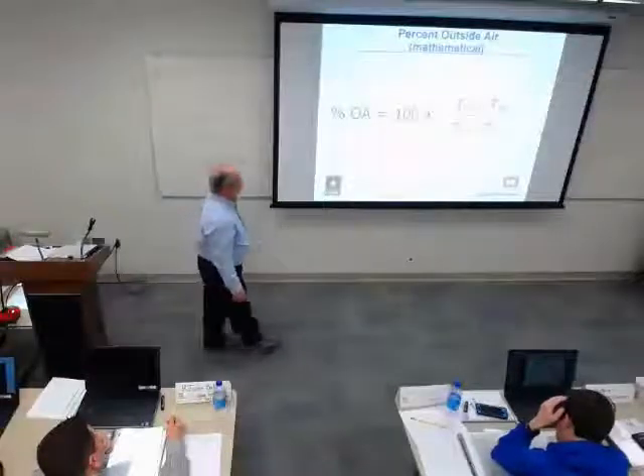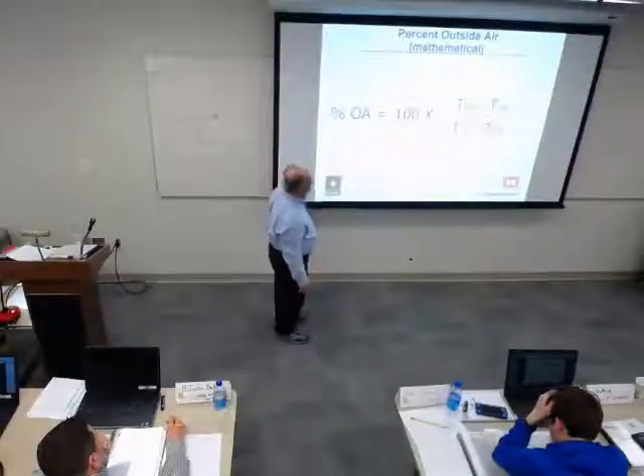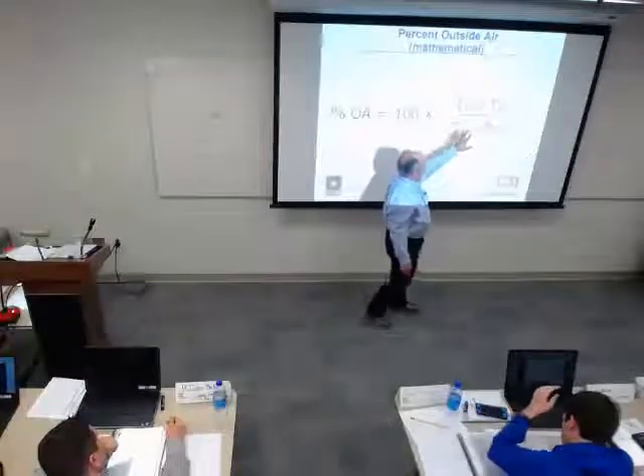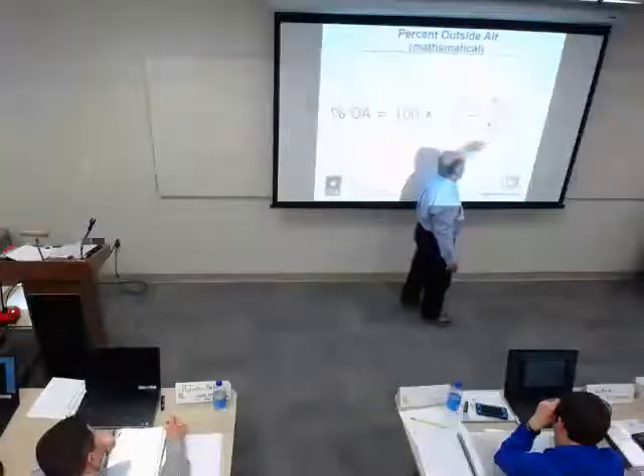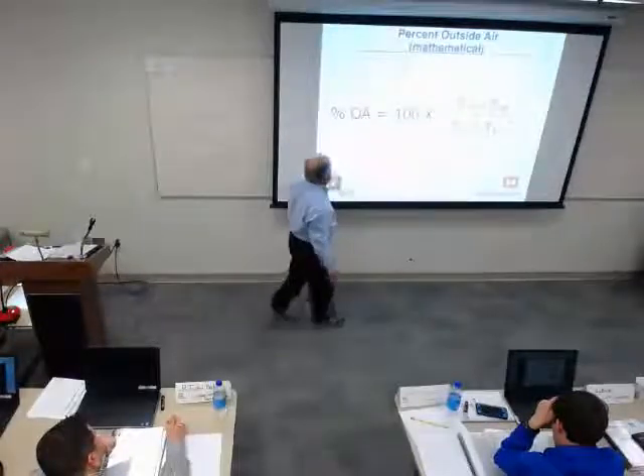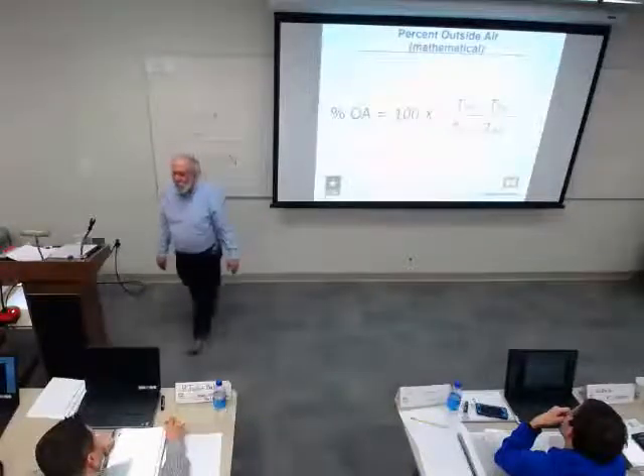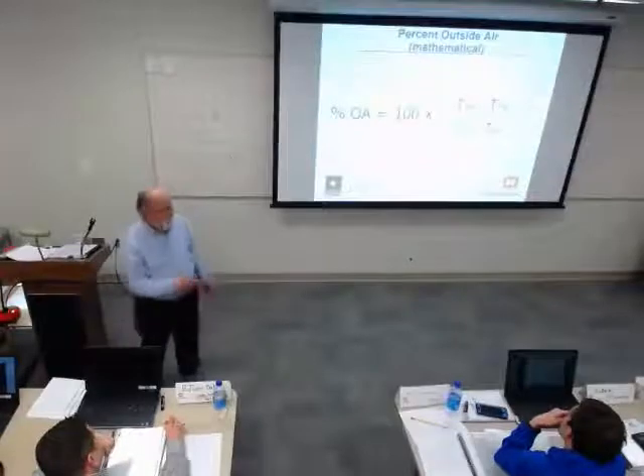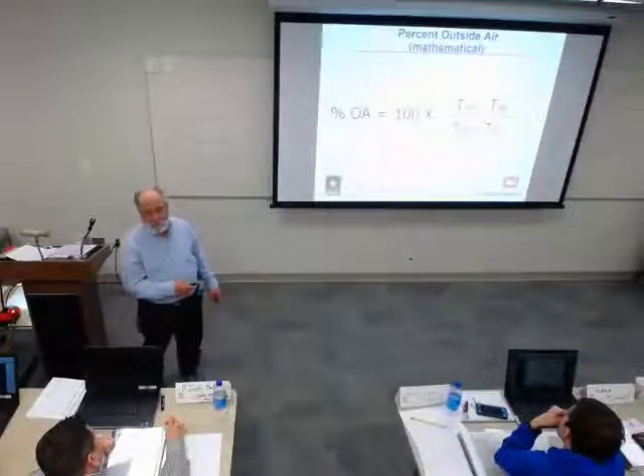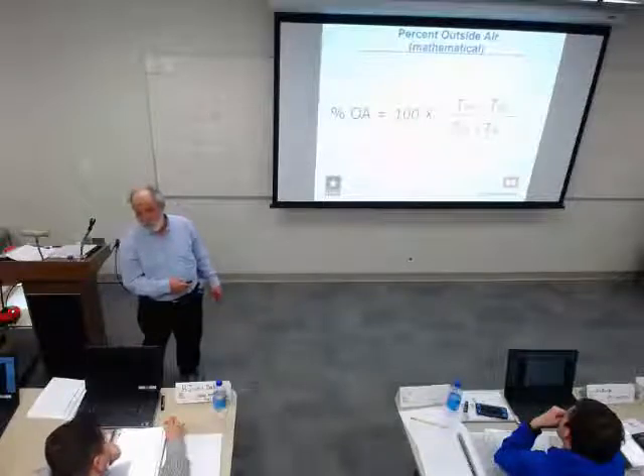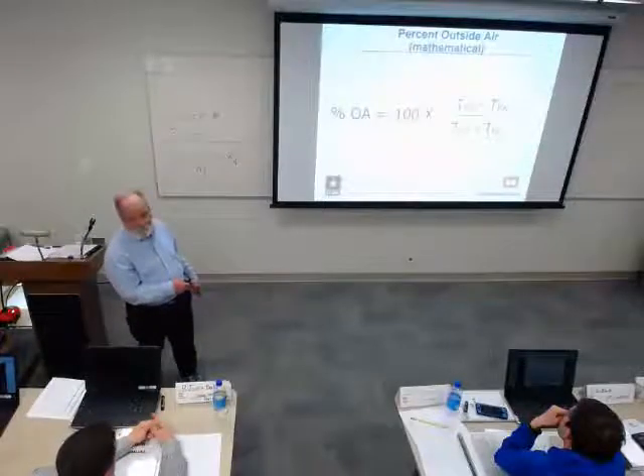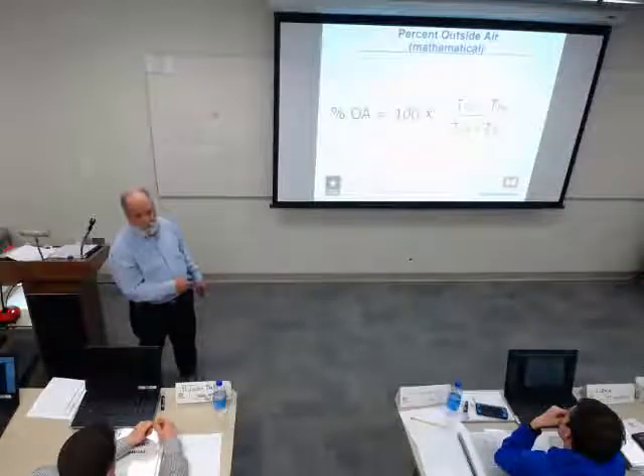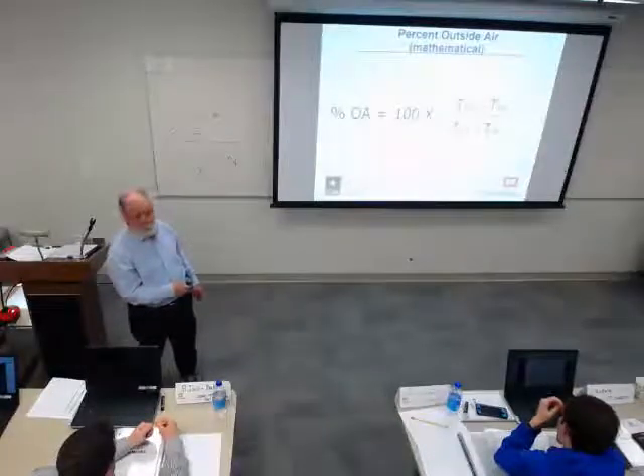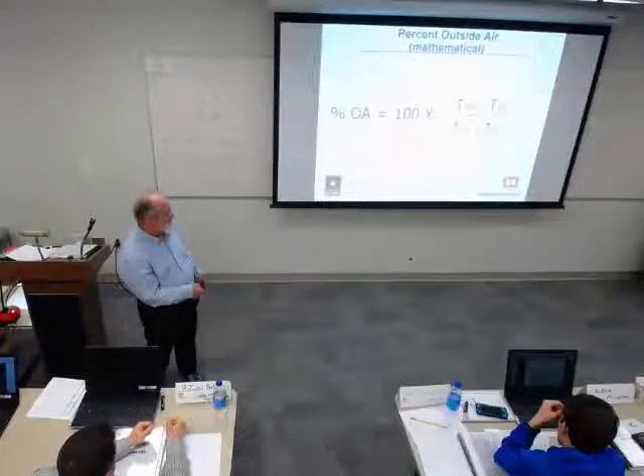So if we want to know the percentages, we take the temperature of the mixed air minus the temperature of the return air, divide that by the temperature of the outside air minus the temperature of the return air, and multiply that times 100 for 100%. That gives us our percent of outside air. And that's a useful thing to know sometimes. It used to be a key thing to know because we wanted to have a certain percent outside air. Now it's just a useful thing to check things with. There are times when you know that percent up front, or otherwise you want to see if things are reasonable. And that's a good, fast reasonability check.